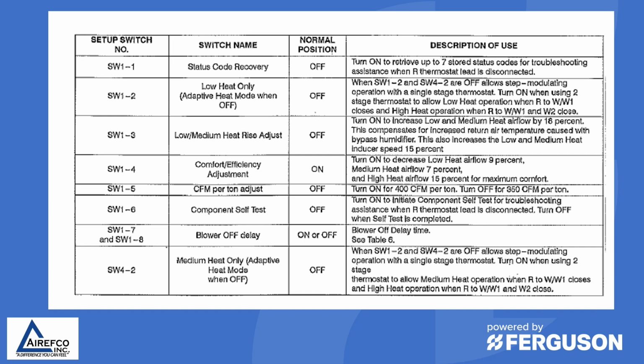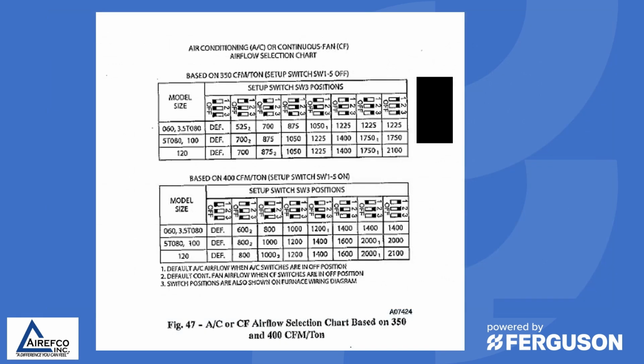When working with these ECM motors, you want to make sure that the dip switches that are on the control board are set correctly. There are charts like these in the installation guides for either the furnace or the air handler, which tell you what you can set the dip switches at for various operating modes. On the furnace or the air handler, you will also have dip switches where you can set up the AC and the constant fan airflow selection. Make sure you set these correctly for the tonnage equipment that you're working with.